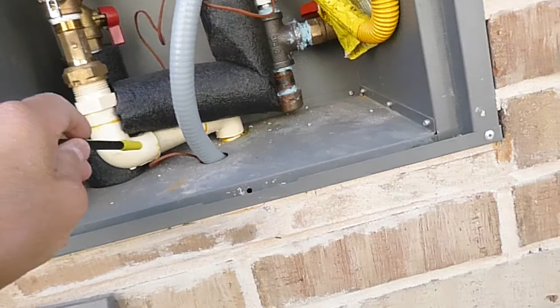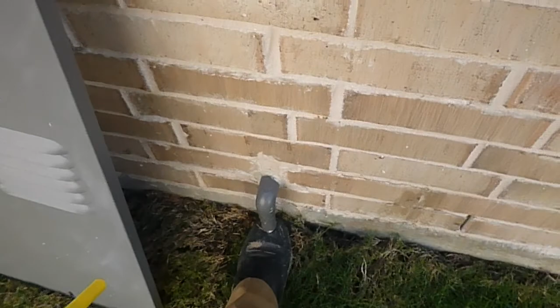You don't have pressure relief valves—excuse me, you do have pressure relief valves, but also temperature relief valves. This is the pressure relief valve for the tankless water heater, and when that drain terminates toward the ground like this, there's supposed to be a minimum of 3 inches and a maximum of 6 inches of clearance. I'm thinking we've got 3 inches right there. Earlier I was thinking differently, but that's why I talked myself through it a couple times.